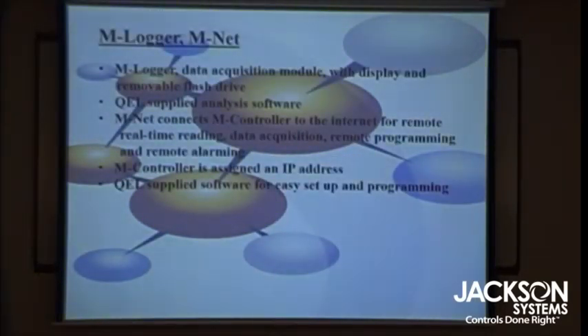The M logger and MNet basically are just optional items. The M logger is just a data logger, and that just records all the concentrations and all the relay activations. It comes with a removable flash drive. We give you the software, so if you want to look up January 30th or December 25th, what happened, it'll tell you all the concentrations, and you choose the window you want to look at. Or there's software in there to tell you, okay, when were there alarms? And it'll go right to where the alarms were.